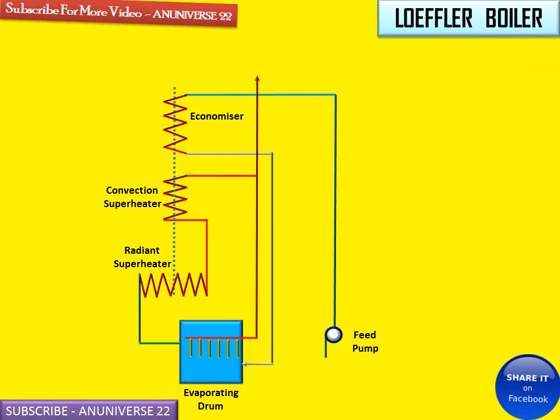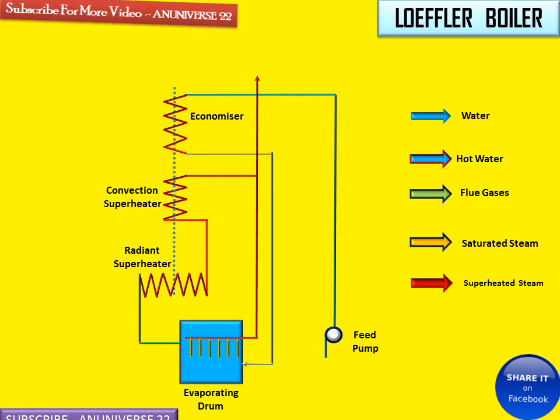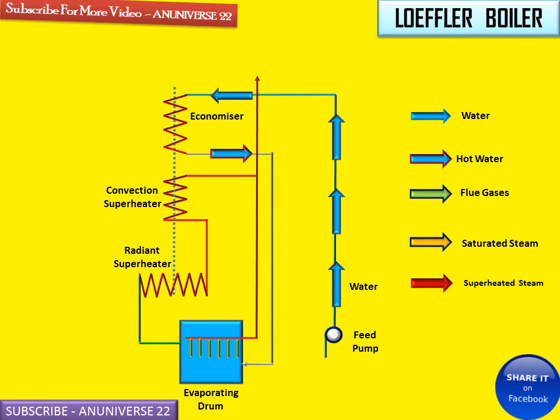This is the diagrammatic view of the Loeffler boiler. The arrows show hot water, saturated steam, and superheated steam — these different arrow types indicate different flow paths. The high pressure feed pump draws water through the economizer; this is the high pressure water supplied to the economizer, and from the economizer this hot water is delivered to the evaporating drum.